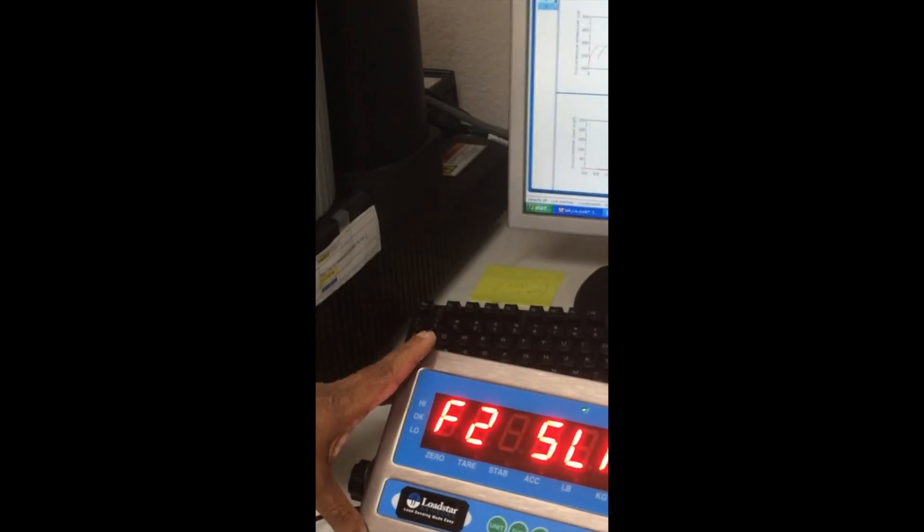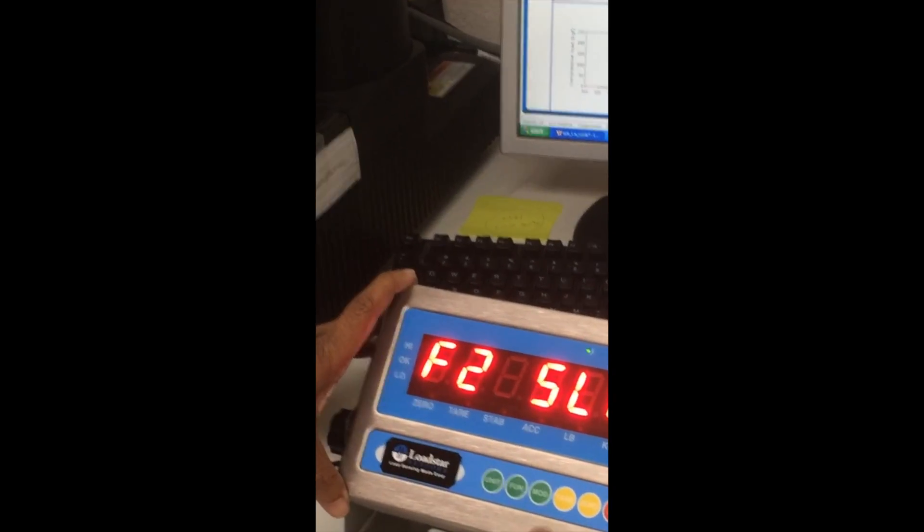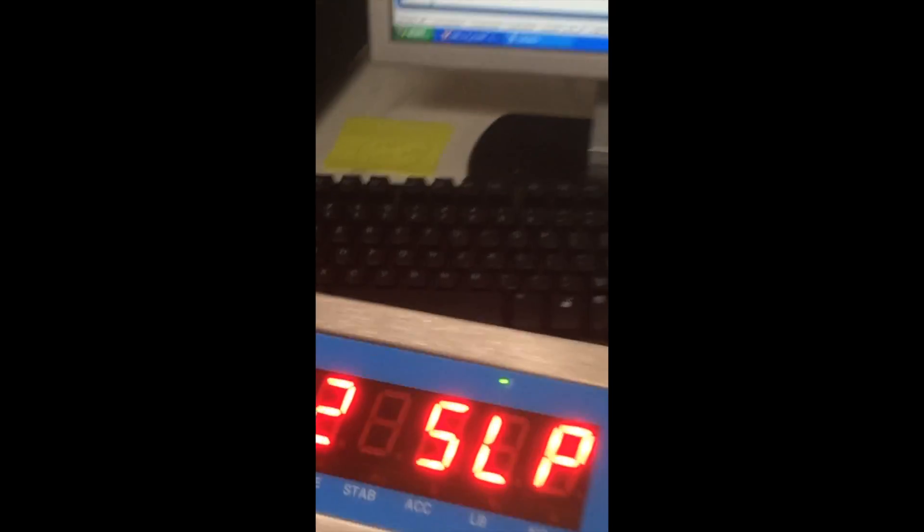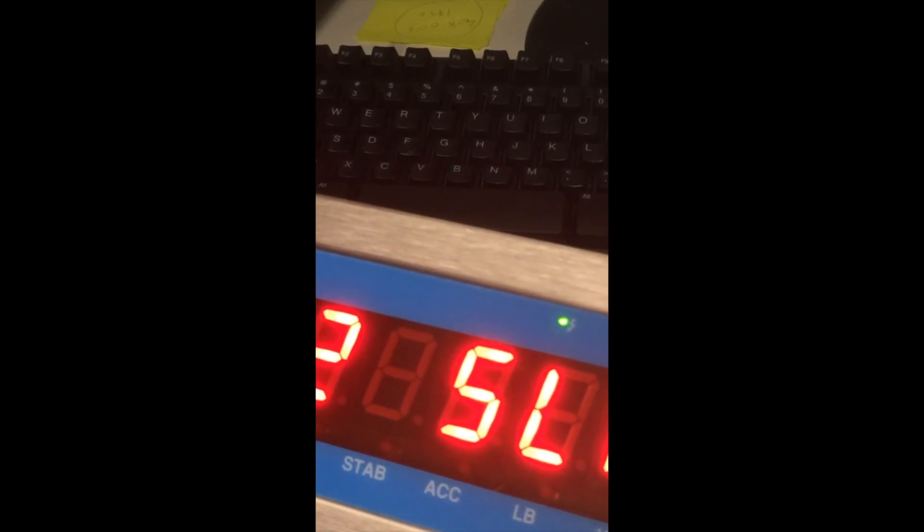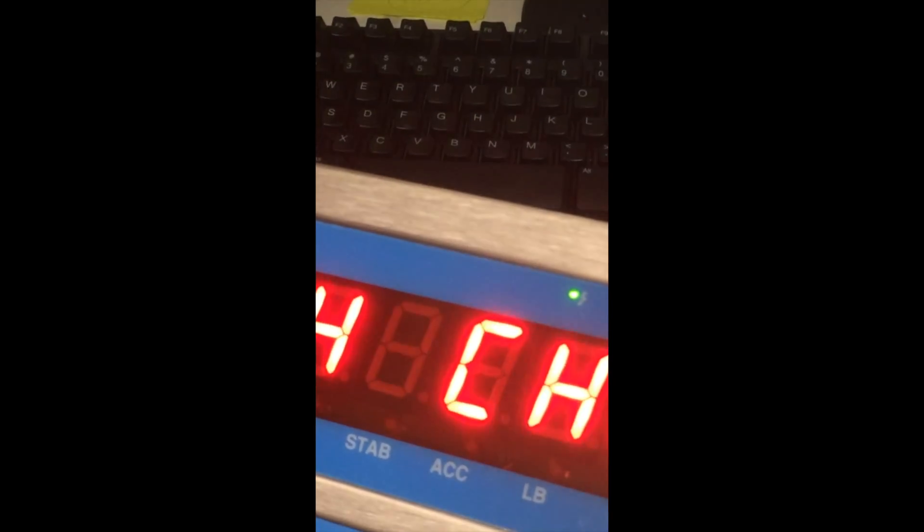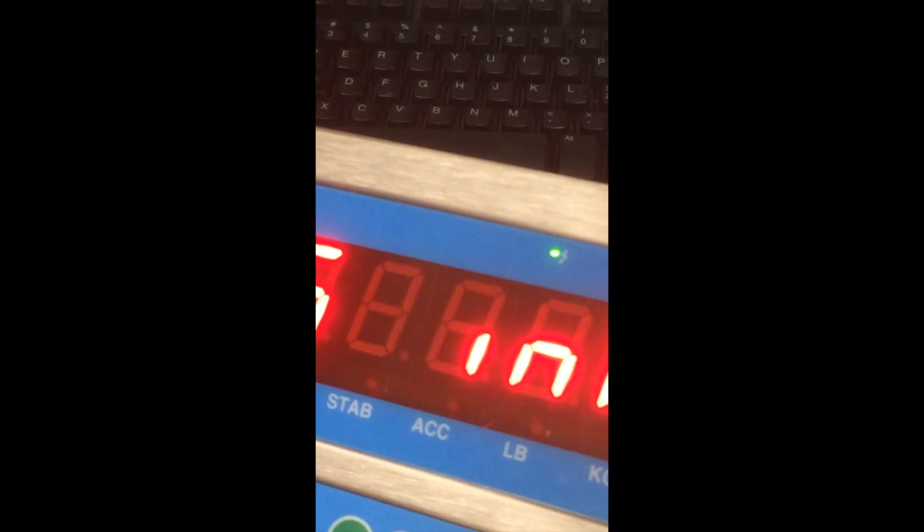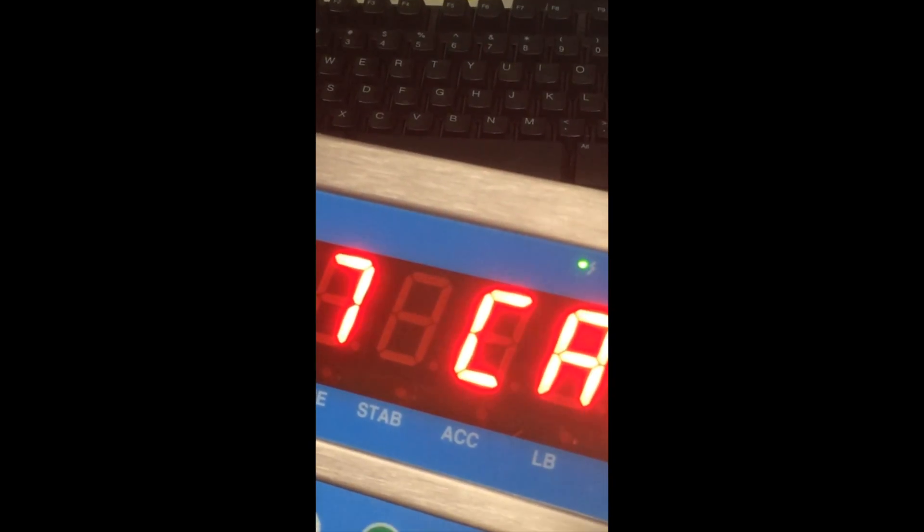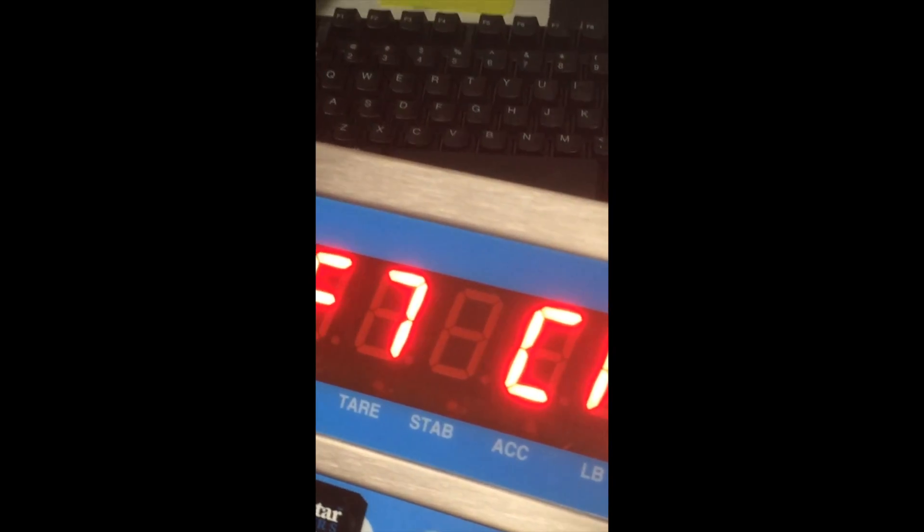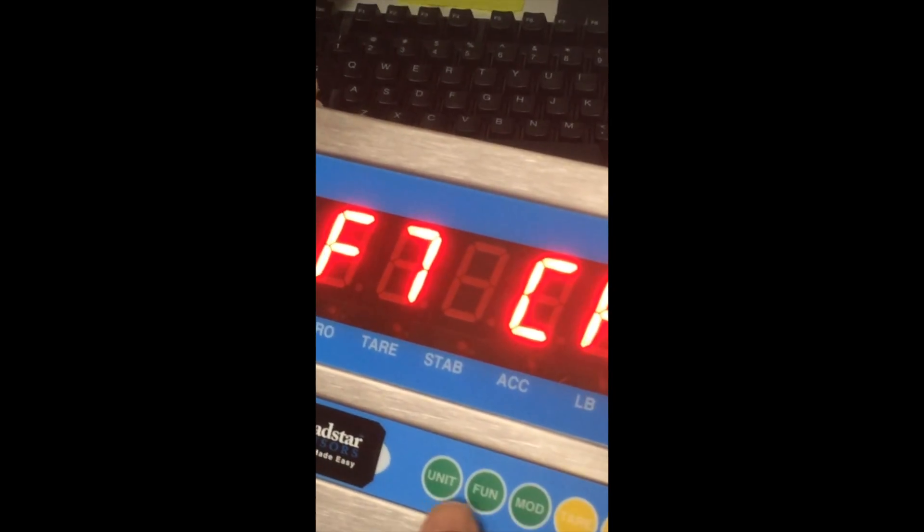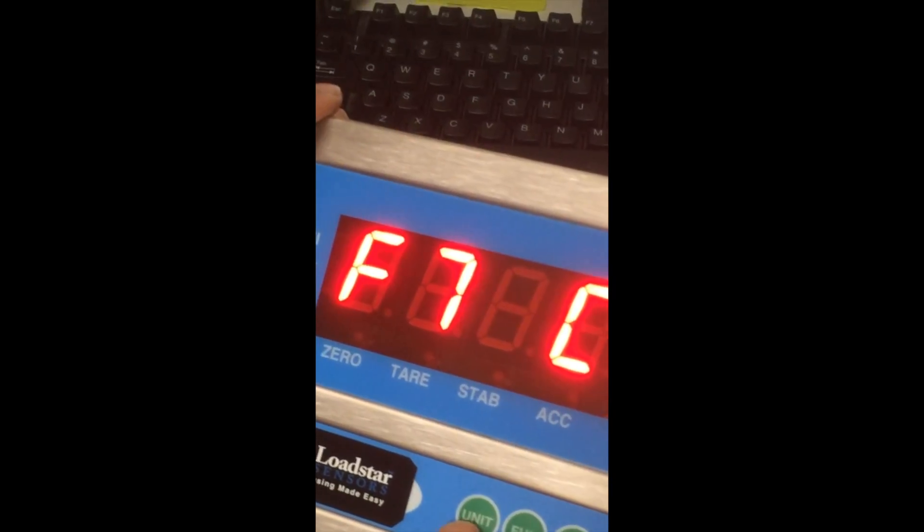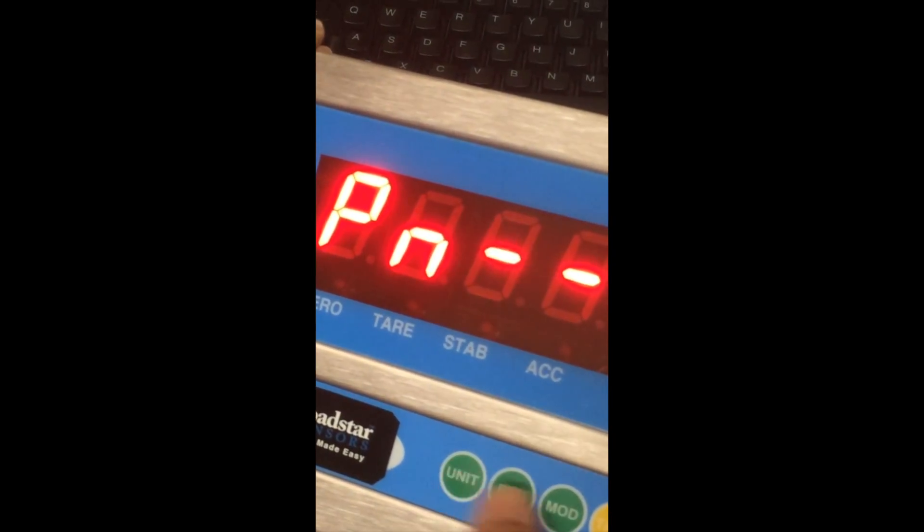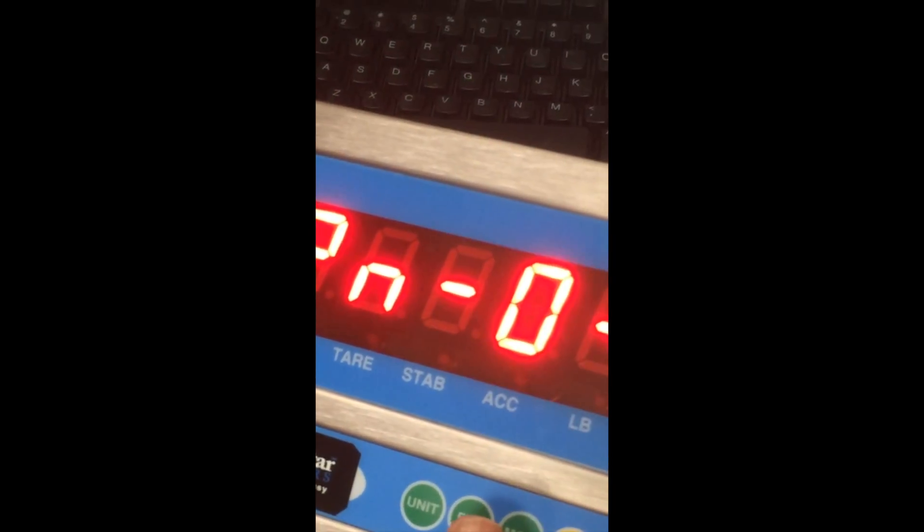I'm going to set the units to kilograms now. So press the tare key, keep pressing the tare key to go to Cal. That should be F7. When you are here, press these keys in quick succession: function, unit, zero, tare.